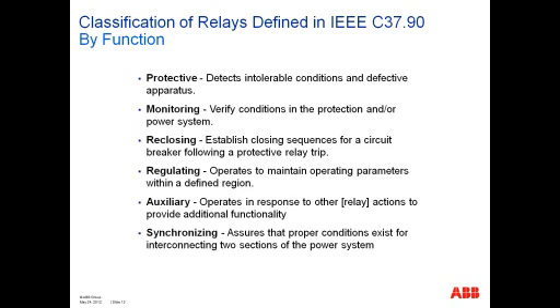There's a classification of relays defined in IEEE standard C37.90. They're defined by protective relays, which detect intolerable conditions and defective apparatus. There are monitoring relays to verify conditions in the protection and/or power system, generally providing some type of alarm for abnormal conditions. There are reclosing relays, which establish the closing sequence for a circuit breaker following a protective relay trip. There are regulating relays which operate to maintain operating parameters, maintaining the voltage level with a voltage regulator, for example, or a voltage regulating tap changer on a transformer. You have auxiliary relays, which operate in response to other relay actions to provide additional functionality, and then synchronizing relays to assure that proper conditions exist on two sides of a breaker before closing it.